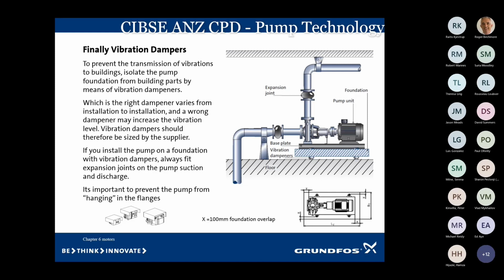One other job we had, it was a little pump, and the engineer thought he'd do a good job. It was a vertical pipe running up a wall, underneath a doctor's office. The pumps were sitting in the vertical pipe with the motors hanging out. They're only small, but he thought, I better safeguard the motors, so he pinned them to the ceiling. Even though the pumps were small, the doctor was in his office one day, and he put his pen on the table, and he watched it roll off the edge of the table, and he couldn't work it out. It was just a very small motor, but because of the way it had been installed, it set up vibration through the ceiling, enough to upset his pen. So vibration can be a real pain in the butt.